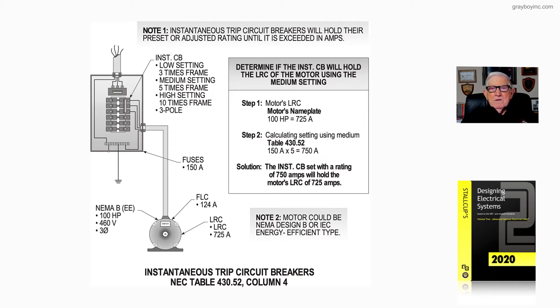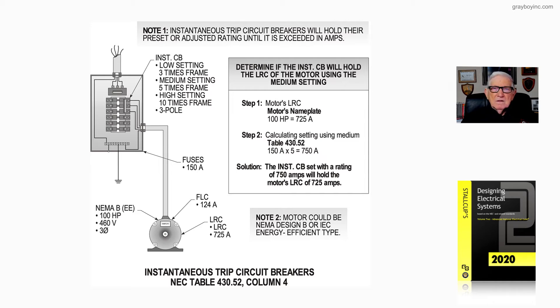Note one basically talks about an instantaneous trip setting — once it's set, that device will not trip until you exceed its setting. Note two points out that this could be a NEMA B high-efficiency motor or a European design E-type motor. You need to identify what type of motor you have so you know what type of device to use to start it, and it's based mainly on design, as we'll see going through chapter 18.